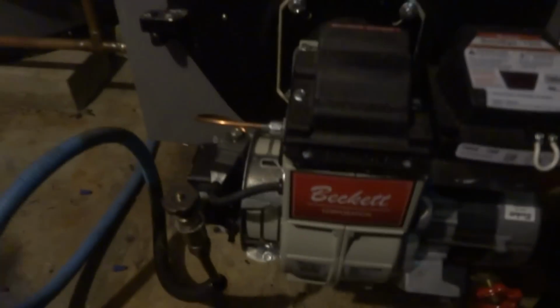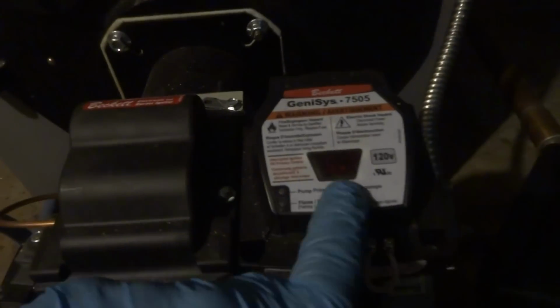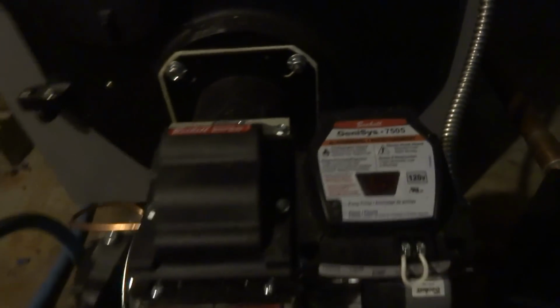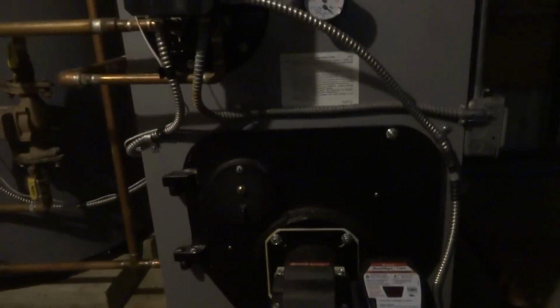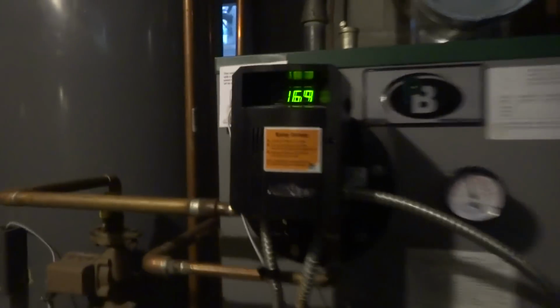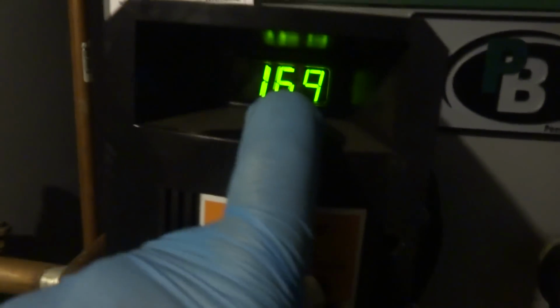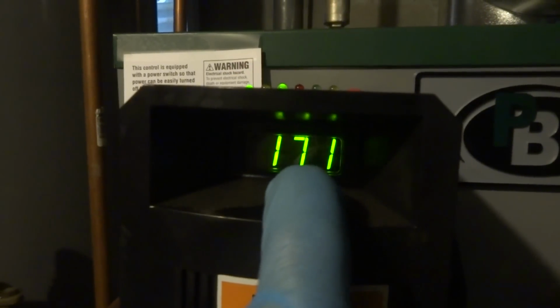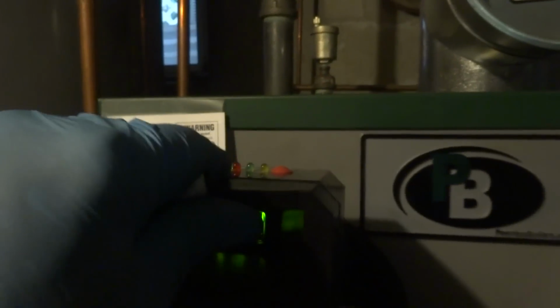Alright, so what we're going to do is I got the burner here. We're going to take it apart and check the nozzle and check our oil flow and whatnot. Because he did say it was tripped out when he got here, then he was here for a couple hours, an hour and a half on a weekend. It didn't come up to speed. It would come up to like 110, 120 and shut off, he said. So I think it might have been the low water issue with this probe.